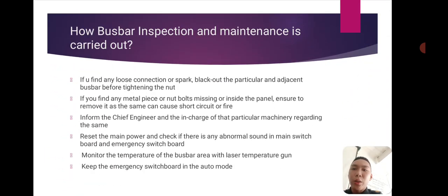If you find any loose connection or spark, black out the particular and adjacent bus bars before tightening the nut. And if you find any metal piece or nut bolts missing inside the panel, ensure to remove it, as the same can cause short circuit or fire. Inform the chief engineer and the person in charge of that particular machinery regarding the same.